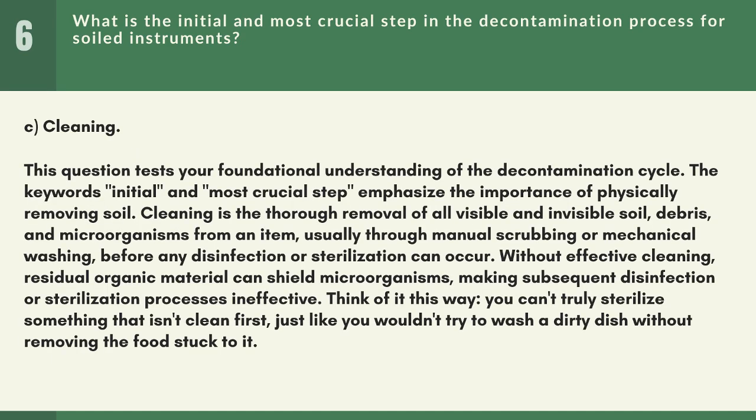Answer: C. Cleaning. This question tests your foundational understanding of the decontamination cycle. The keywords initial and most crucial step emphasize the importance of physically removing soil. Cleaning is the thorough removal of all visible and invisible soil, debris, and microorganisms from an item, usually through manual scrubbing or mechanical washing, before any disinfection or sterilization can occur.